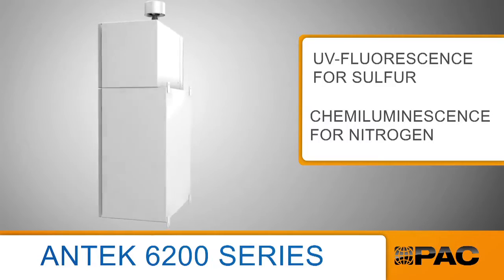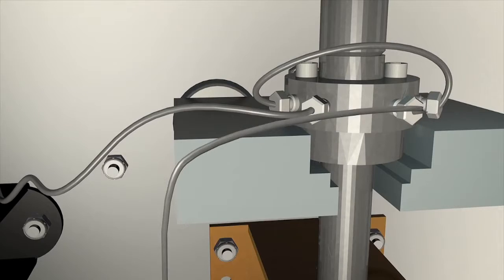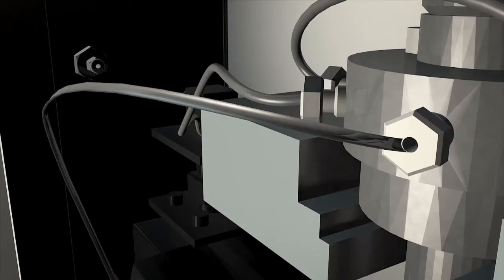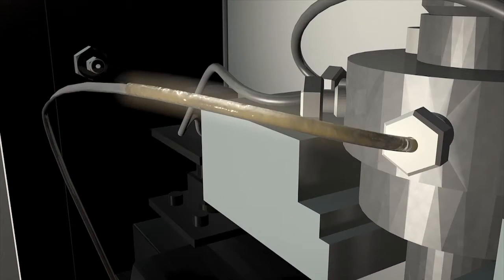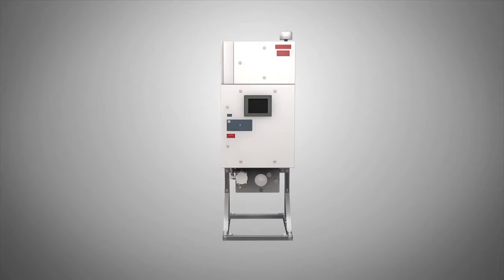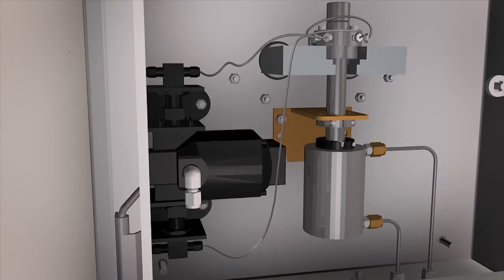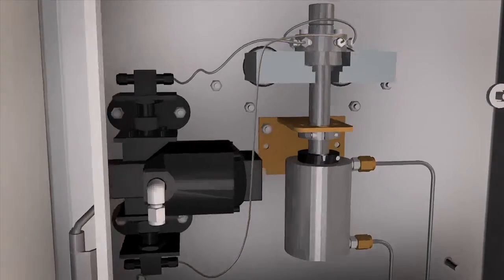The first step is the introduction of the sample. The 6200 series utilizes a direct injection system which means the sample is completely combusted during every measurement cycle. The injection valve directly delivers a microliter of sample to the furnace for analysis.